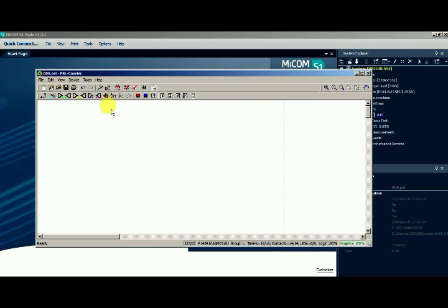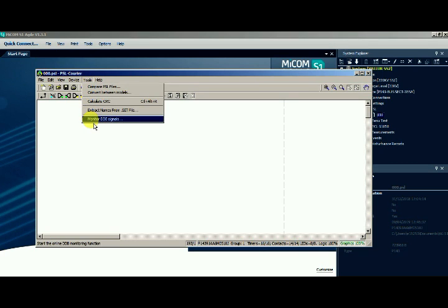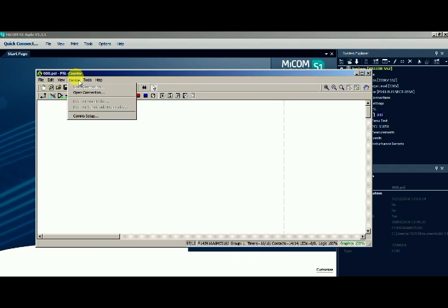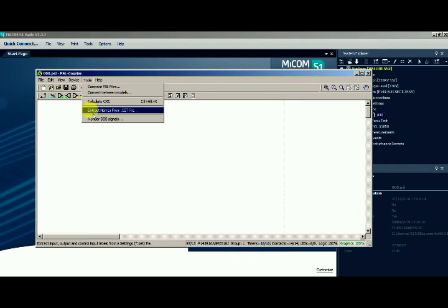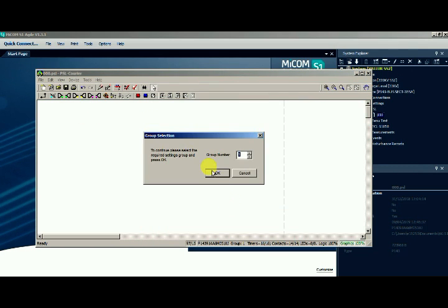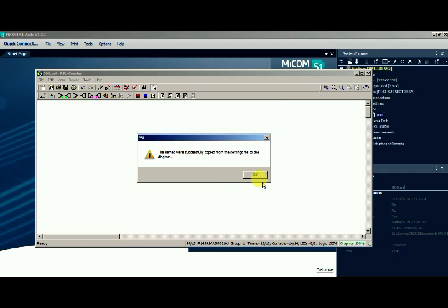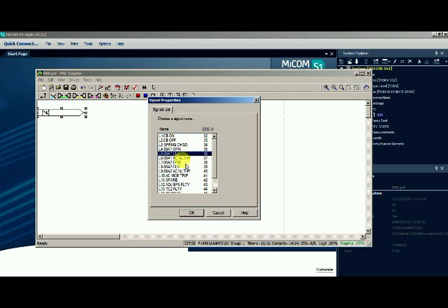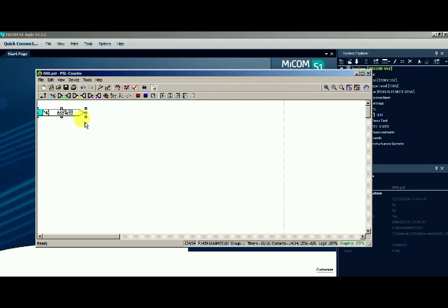If you already assigned naming for binary input and output in a setting sheet, you can extract the name by going into the Tools menu and finding the option to extract naming from the .set file. If you extract the file into this PSL logic sheet, then when you click the binary inputs and outputs you will be able to find the naming which you already assigned. By seeing this name you can easily configure your target.